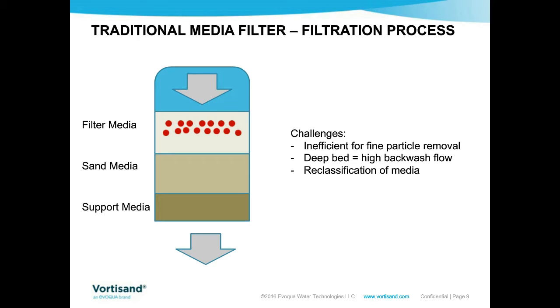Well, sometimes we compensate by adding chemistry, but that adds complexity to the system. We can also compensate for the lack of efficiency at small particle removal by adding one step of treatment. For example, in front of membranes, we will use cartridge filters. But that leads to increased operating costs because those cartridge filters plug up quickly and need to be replaced. So the inventor of CROSSFLOW microsand filtration, an engineer called Guilford Sharrow, in 1962 said, well, there must be a better way. I would like to be able to use a finer media to remove the fine particles. And he did try it, and he introduced microsand as a media.